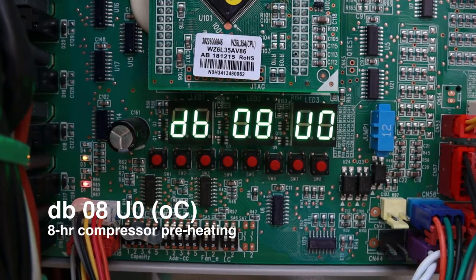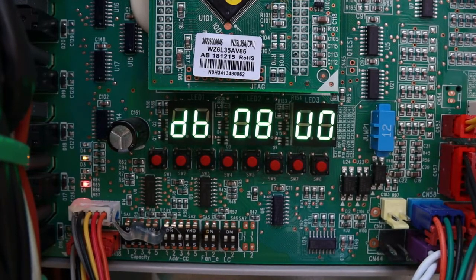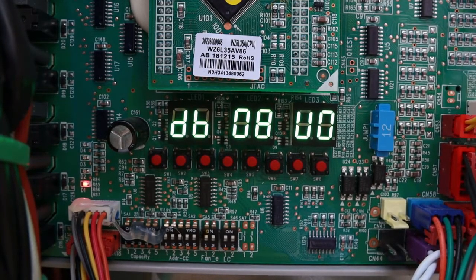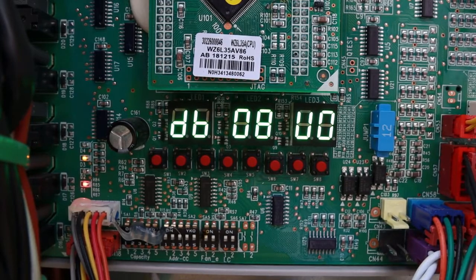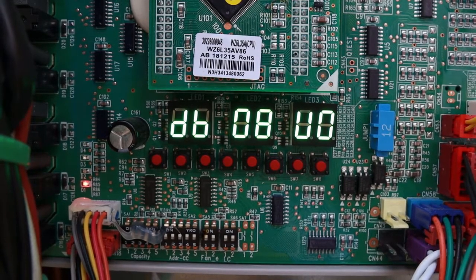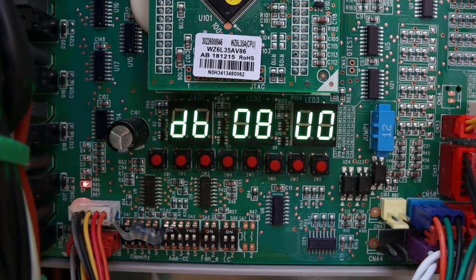I always recommend to wait the 8 hours. Do not try to force it. Do not try to skip it. Just give it 8 hours for the system to do its job, which is to extract any oil that could have mixed, or actually any refrigerant that could have mixed with the oil. So 8 hours. Guys, just wait 8 hours until the system does its thing, and then we're ready to go.